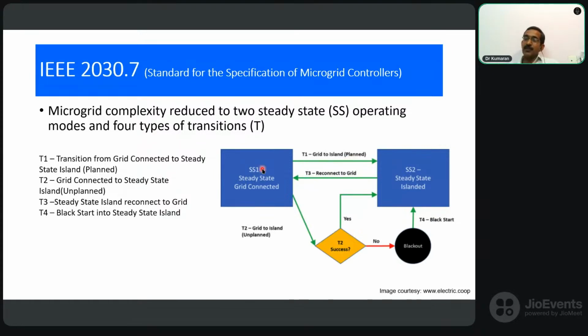There might be other transitions from grid connected to islanded state which are unplanned, happening all of a sudden for some reason, such as the power from the grid becoming unavailable. Under these cases, we have to transit to islanded mode, and this transition can either be a success or not. We may not have the required number of generating stations online in our microgrid at that time, since we don't know it will happen we cannot keep the power stations running, unless it's something like battery energy storage, or a solar plant during peak daytime.